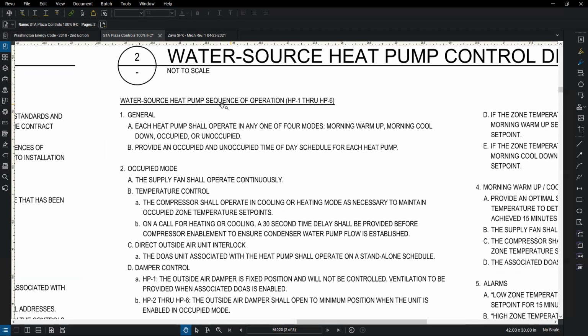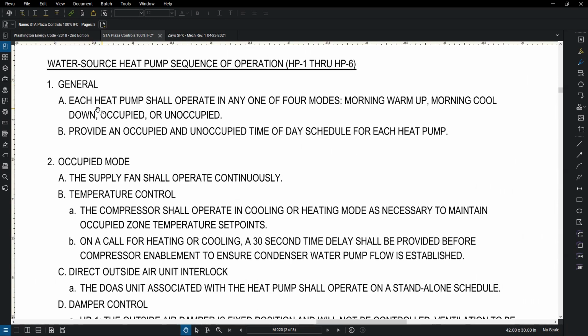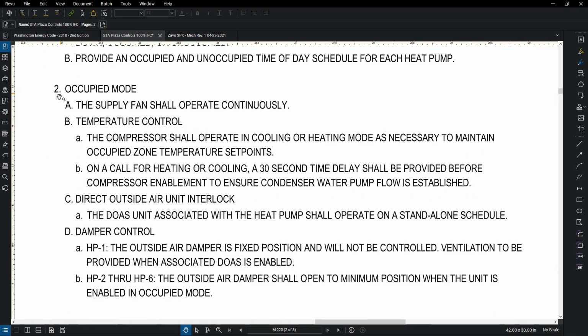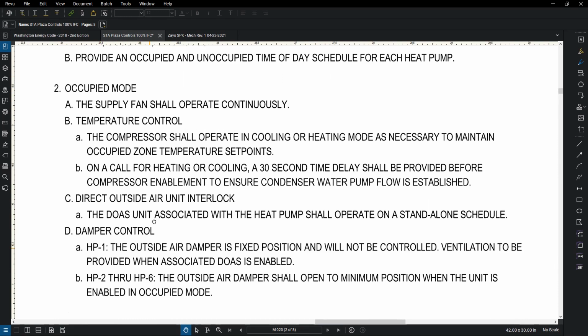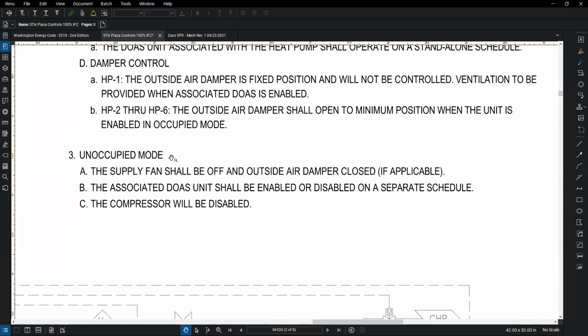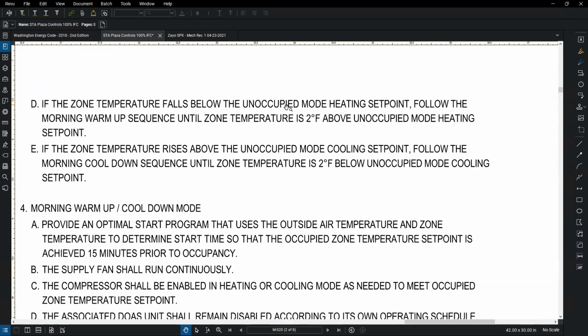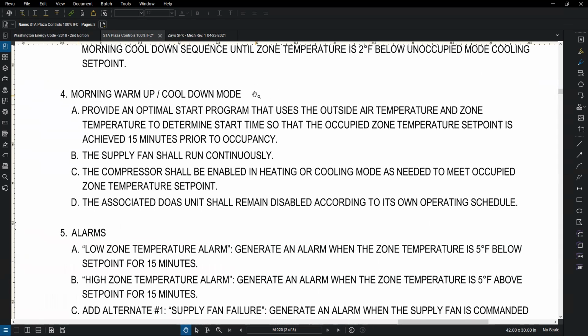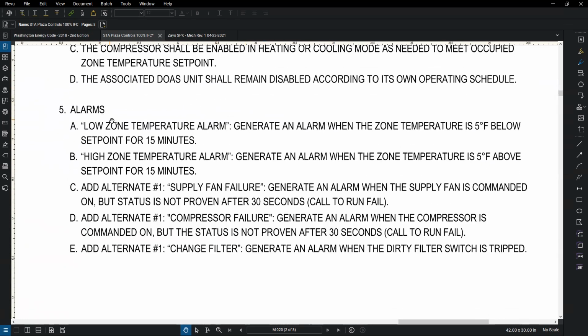Then you get into the sequence of operation. And this is essentially a narrative description of how this thing is supposed to run. So you can see here, under the general, each heat pump shall operate in any one of 4 modes. Well, you know what morning warm up, morning cool down, occupied and unoccupied mode all mean. And those are the 4 modes this could be running in. And when we're in occupied mode, here's what should happen. Here's what the dampers should do. If we're in unoccupied mode, here's what should happen. Basically, everything should be off, unless the zone temperature falls outside of those unoccupied set points. Then we need to tell it what to do. Morning warm up and cool down, we describe what needs to happen there. And then all of the alarms we want to see.